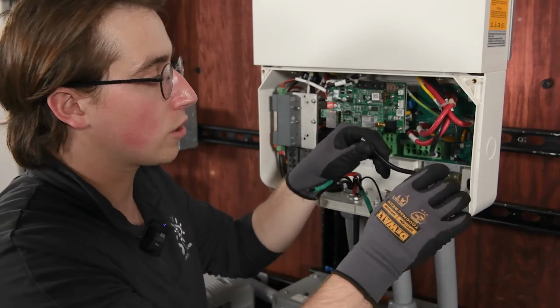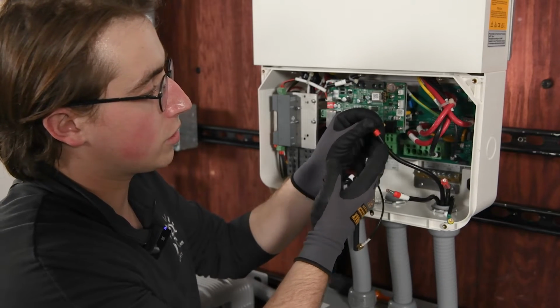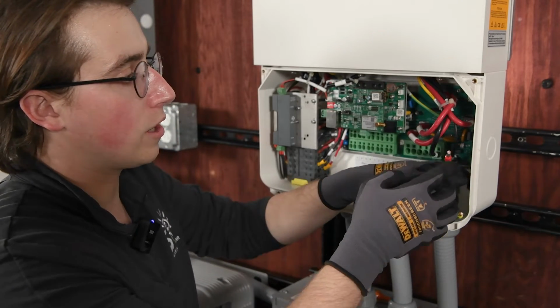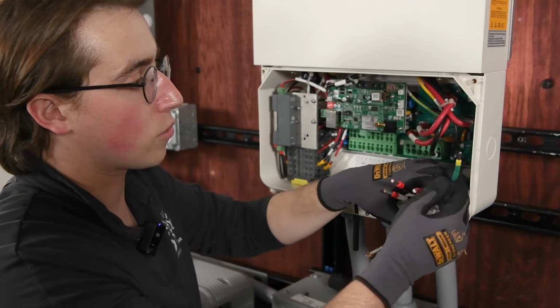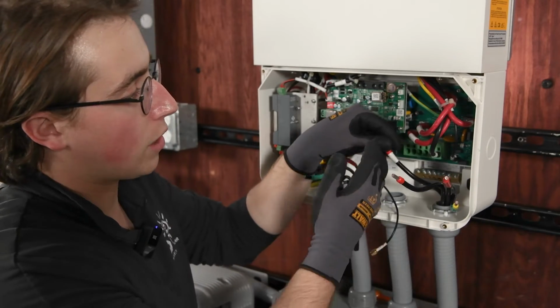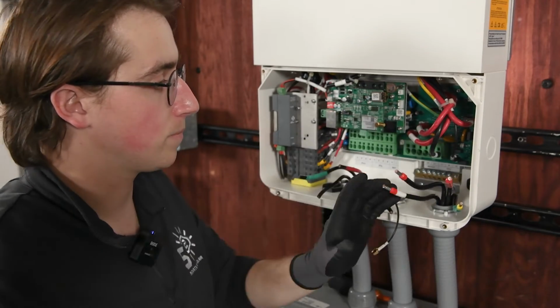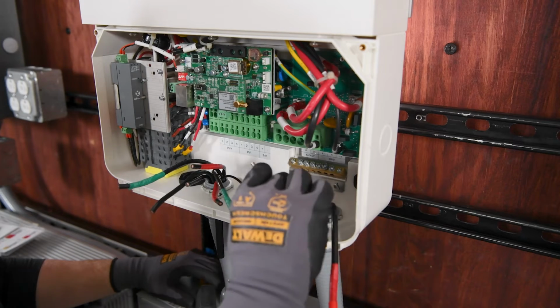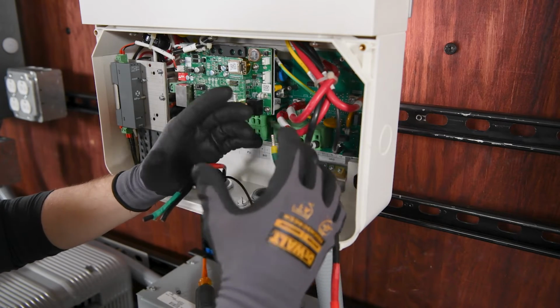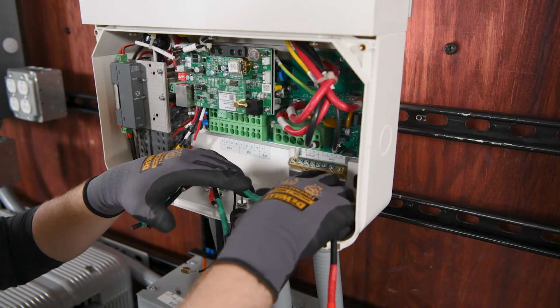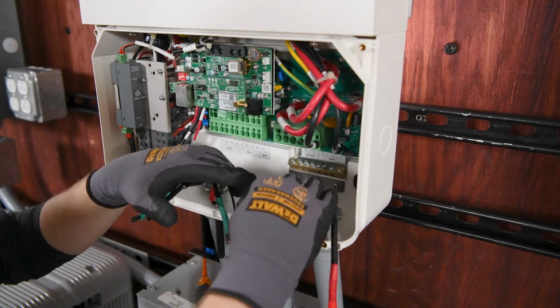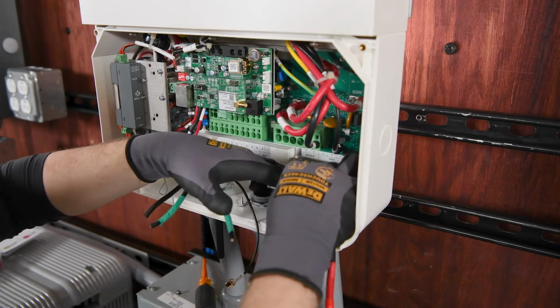So a simple color coding is our L1 is just the straight black jacket, our L2 is going to be red, our green is going to be ground, and our neutral is going to be white. First, we'll connect our grounding conductor. The ferrule is going to make all of those strands stay nice and connected together. We don't want any loose strands not making full contact within the terminal itself.